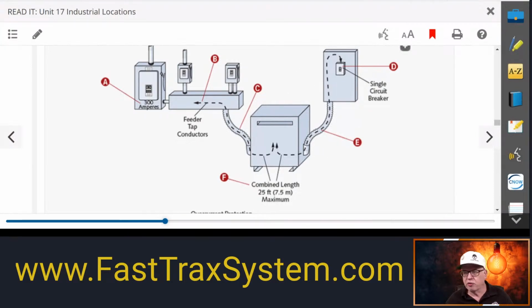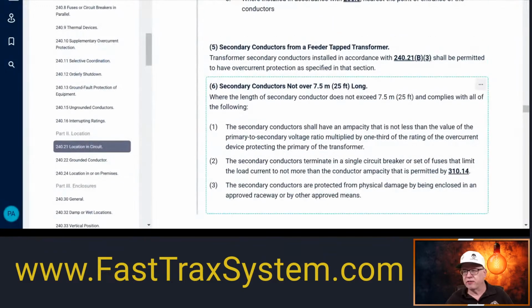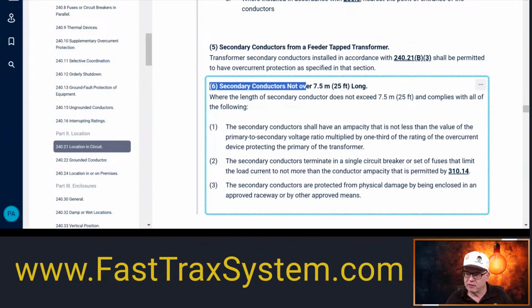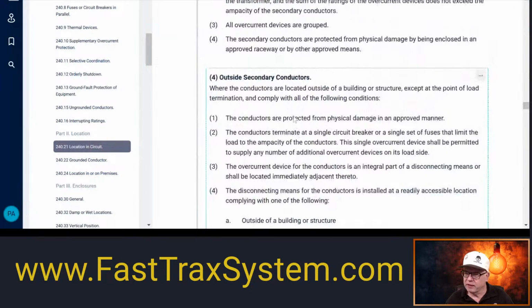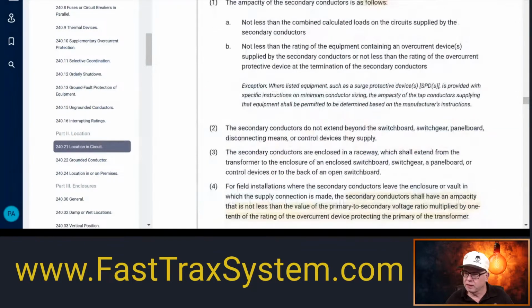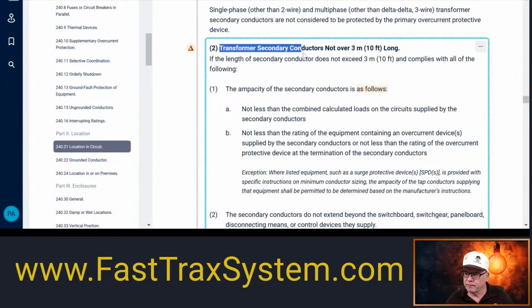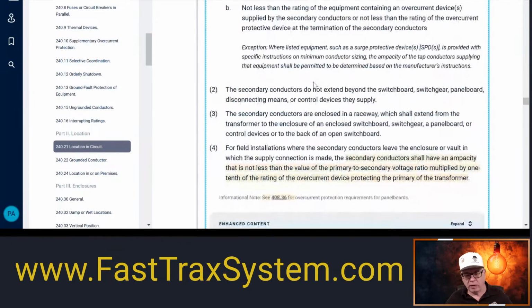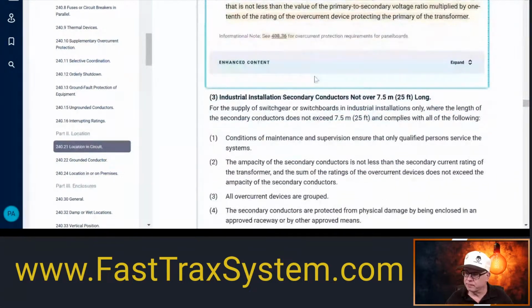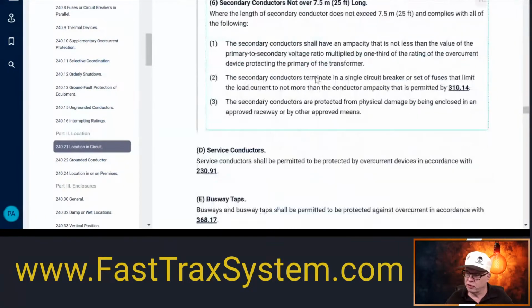Now those conductors are the secondary conductors, and this would be 240.21(C)(6) right here. These secondary conductors. So we went over this rule. This was the 10-foot rule. We went over that rule, I think it was yesterday's coffee hour. So if you haven't seen that, go back and watch a previous episode. And now we want to jump to this one.